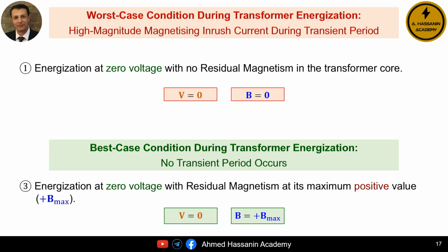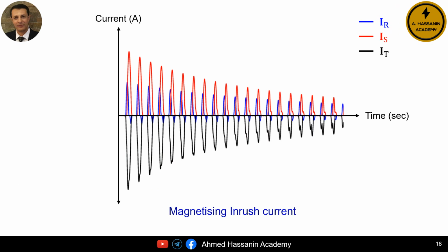However, the best and most stable case for energizing the transformer is the third case, energizing the transformer when the voltage is 0 and there is a residual magnetism in the iron core at its maximum positive value. The shape of the magnetizing inrush current is shown in front of us, and as I mentioned before, it is a distorted wave that contains second and third harmonics, and so on, in addition to the DC component of the current. As we can see, the current for each phase is different from the other phases.